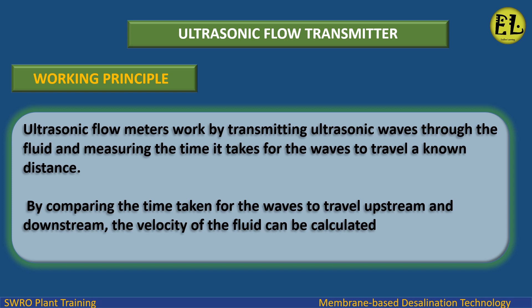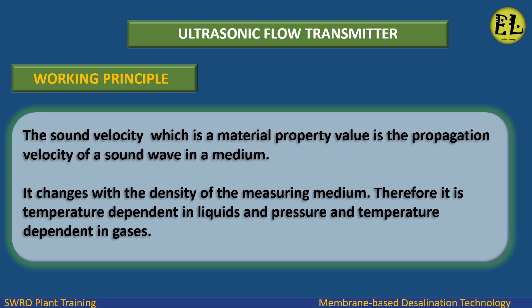Working principle: Ultrasonic flow meters work by transmitting ultrasonic waves through the fluid and measuring the time it takes for the waves to travel a known distance. By comparing the time taken for the waves to travel upstream and downstream, the velocity of the fluid can be calculated. The sound velocity, which is a material property value, is the propagation velocity of a sound wave in a medium. It changes with the density of the measuring medium, and is therefore temperature dependent in liquids, and pressure and temperature dependent in gases.